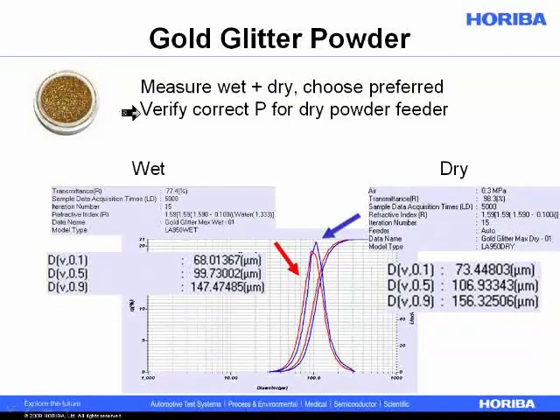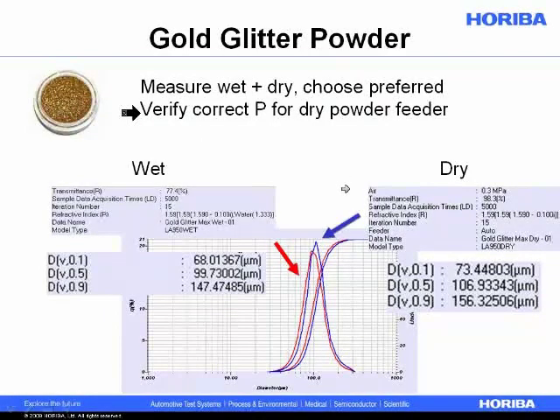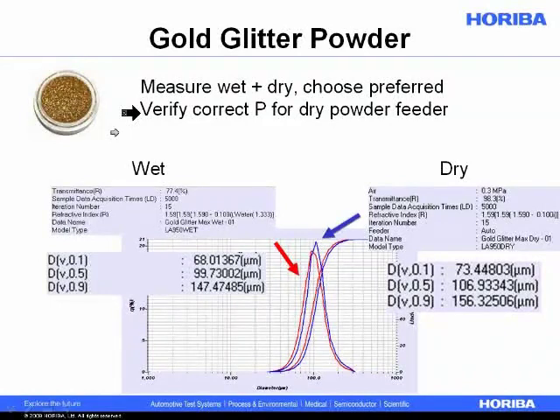Sometimes if we're going to choose to do the measurement dry, it's nice to measure it wet as well to verify the dry result makes sense. It might also help us choose the correct pressure for the dry powder feeder. In this case, if we ran up to a slightly higher air pressure and saw a perfect overlay, we might think that is a better pressure. So we also use comparing wet to dry for method development when using the dry powder feeder.